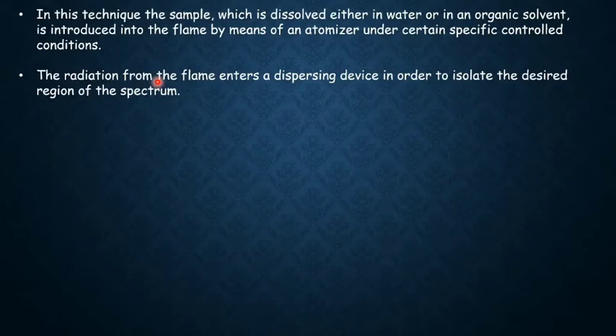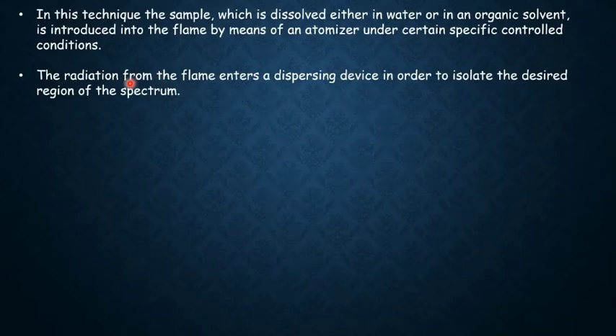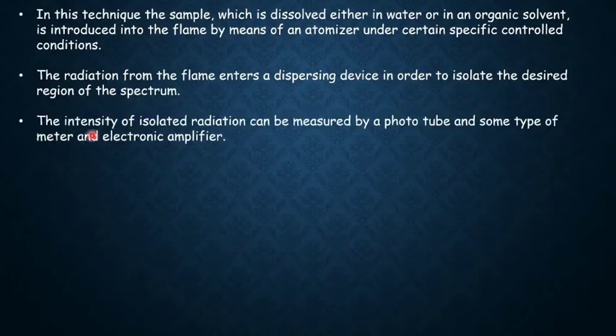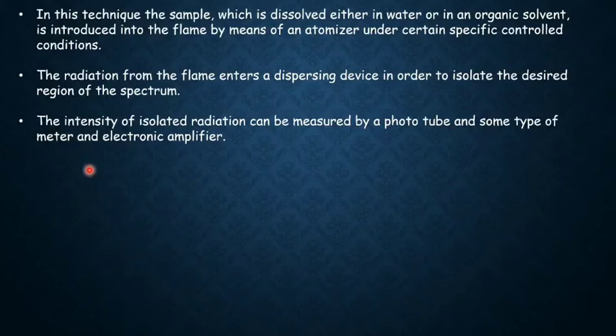After vaporization, dissociation of solid particles occurs to form neutral atoms or free radicals. These atoms then get excited, and after that radiation from the flame enters the dispersing device in order to isolate the desired region of the spectra. The intensity of isolated radiation can be measured by a phototube and some type of meter and electronic amplifier.